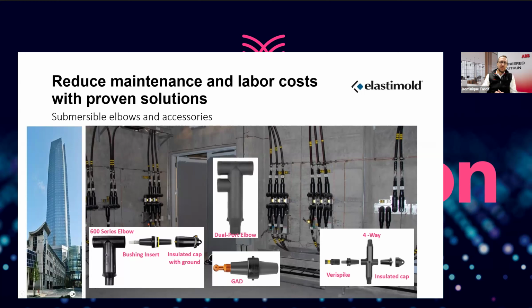You've got a vaulted room somewhere cordoned off, probably in the corner of a parking garage or in the basement of a building. It could be prone to flooding, but it allows you to fit all kinds of cabling and connectivity configurations into a tight space, giving flexibility. If you've got a problem on one circuit, you can quickly disconnect and reconnect, like plugging from one to the other. The Elastimold product line has a whole range of ground aid devices, insulating caps, and bushing inserts for equipment testing and measuring. There are also specialized elbows that reduce space, and I, Y, and H connectors, all designed to use the least space possible in a restrained area while giving the most connectivity options to modify, resource, or reorient the electricity quickly.